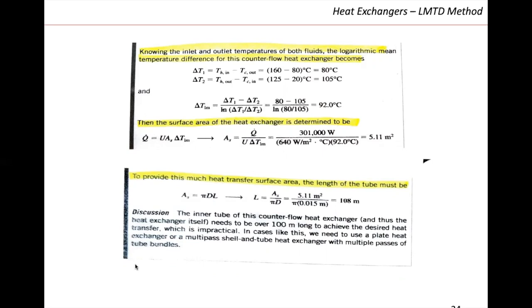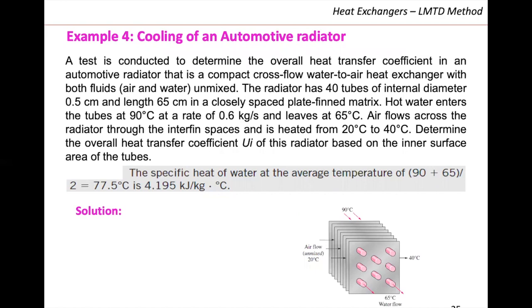The inner tube of this counterflow heat exchanger needs to be over 100 meters long to achieve the desired heat transfer, which is impractical. In cases like this, we need to use a plate heat exchanger or a multi-pass shell-and-tube heat exchanger with multiple tube bundles. So we need to design a shell-and-tube heat exchanger to make this heat transfer rate possible. I'm trying to solve each type of heat exchanger you can face with this method.